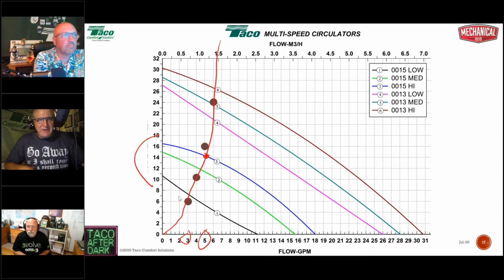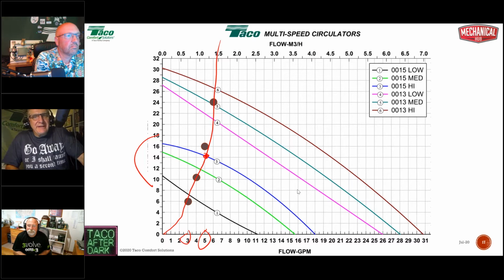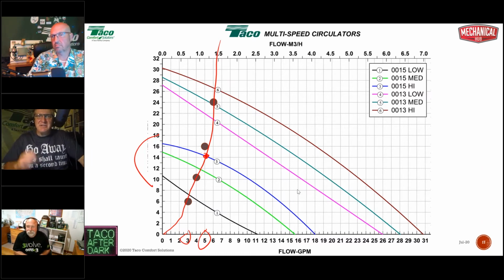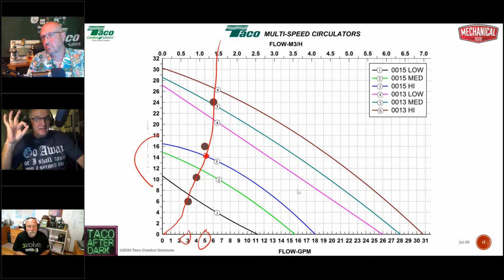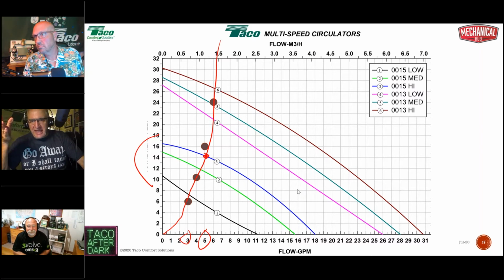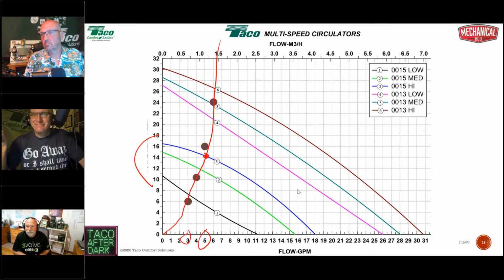Is the passage about 3/4 inch through the 0015 pump? Is that why the max flow is 31 gallons a minute on the 0015? No, it really has to do with just the speed of the impeller and the hydraulics of the circulator. You're kind of bouncing around, but that makes sense. It's not so much the size of the passage, because you give me something big enough, 3/4 inch, I can cram some flow through it. That's just the capability of the circulator at the RPM it's doing. So it can do 30 gallons a minute at about half a foot of head. Well, it's going to get you about 18 actually for the 0015.